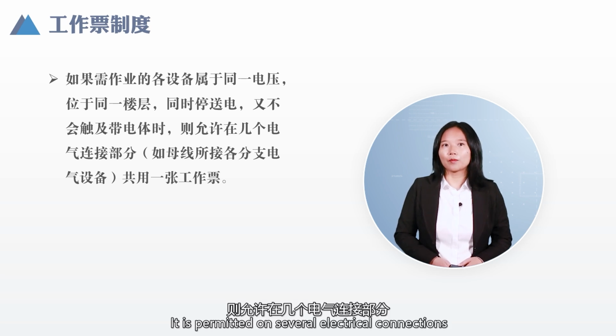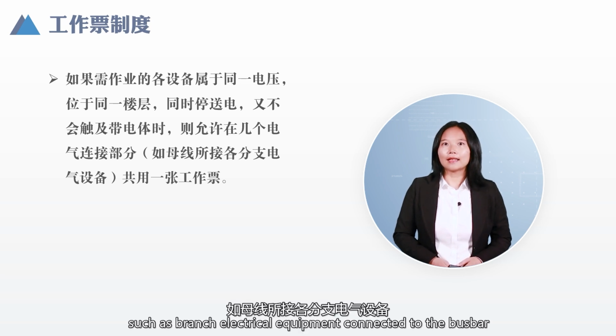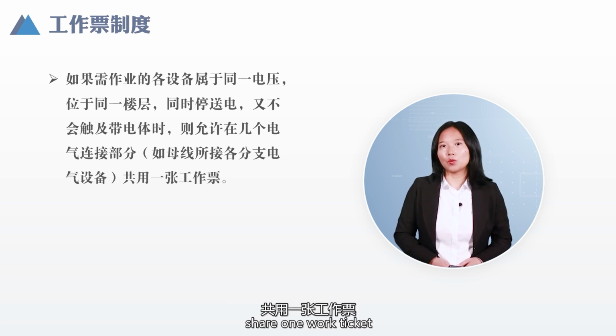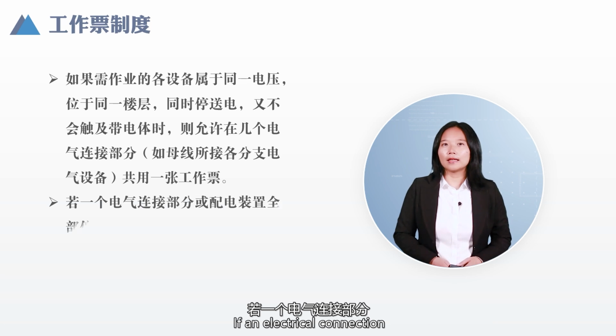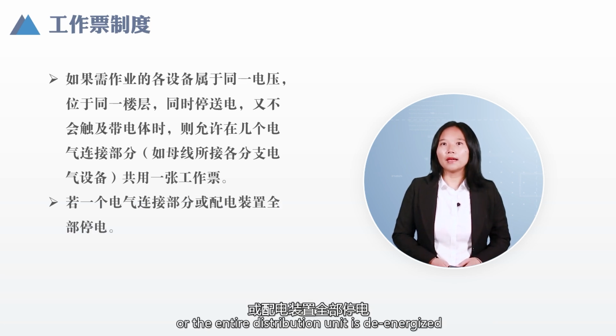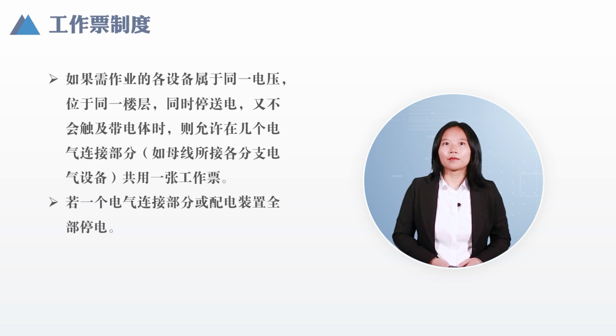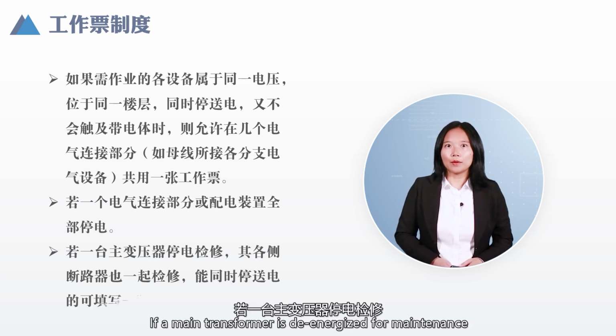It is permitted that several electrical connections, such as branch electrical equipment connected to the bus bar, share one work ticket. This also applies if an electrical connection or the entire distribution unit is de-energized, or if a main transformer is de-energized for maintenance.